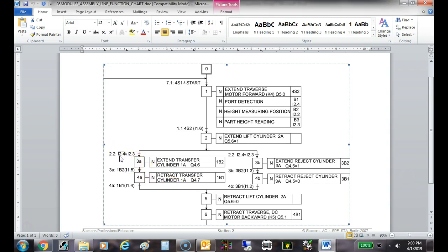If input 2.4, I wish that instead of putting the actual input, they should have put the actual sensor number over here. You see what I'm talking about? So instead of putting B1 over here, they actually put input 2.4. So this says input 2.4 is not true, so it didn't get a reflected light back, right? Understand?